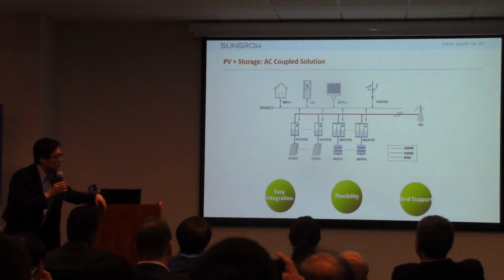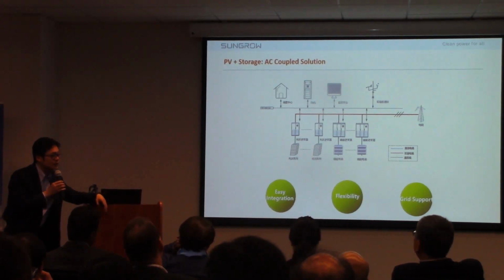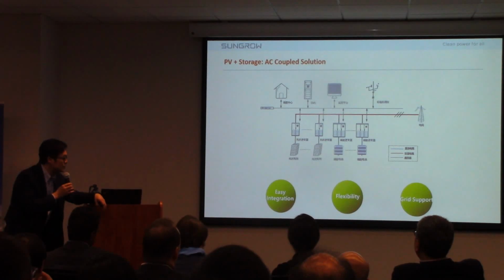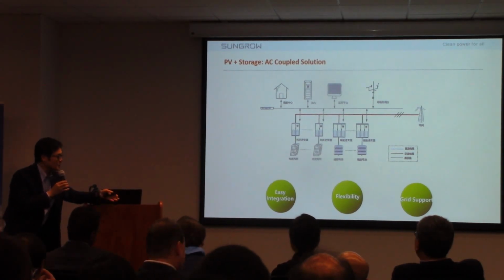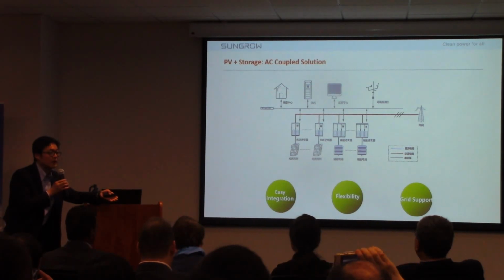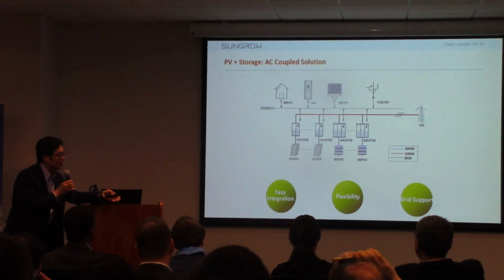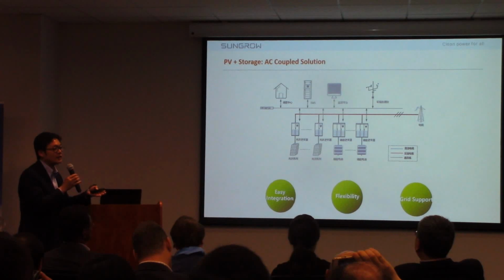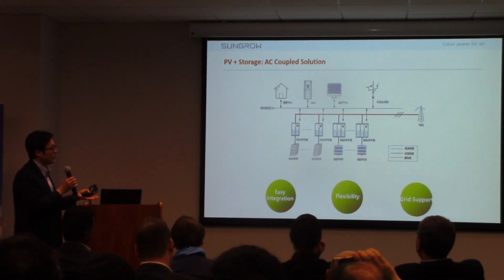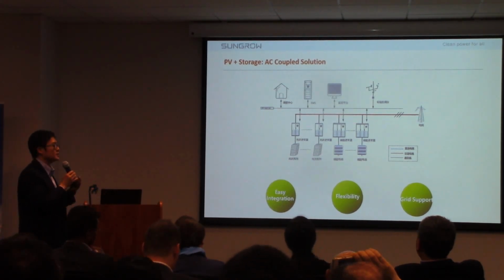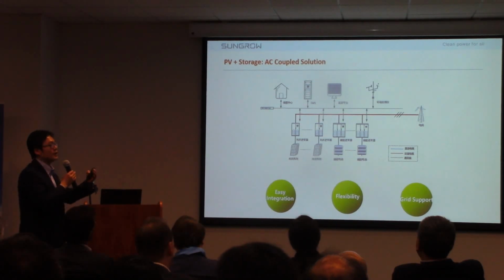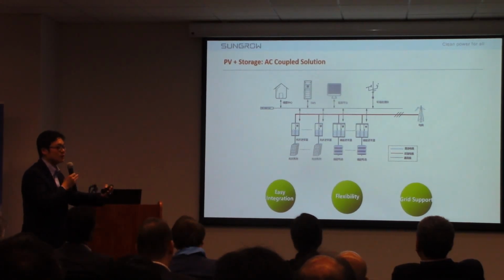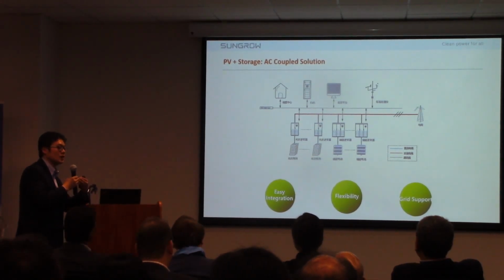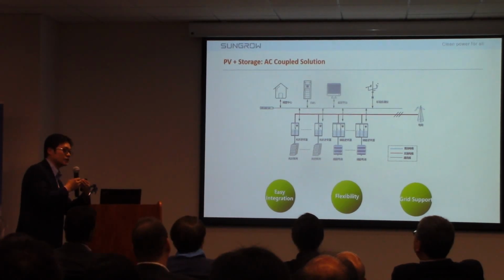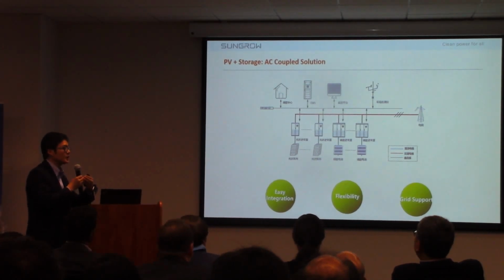First, the AC coupled solution. The benefit is very obvious: easy integration. Since it's AC coupled, you can install it on the AC grid anywhere you want. It also has flexibility, so it can be added anytime you want. And third is grid support—because it's AC connected, you have a lot of interaction, charging and discharging with the grid, so you can help with voltage and frequency regulation. That's the main benefit of the AC coupled solution.